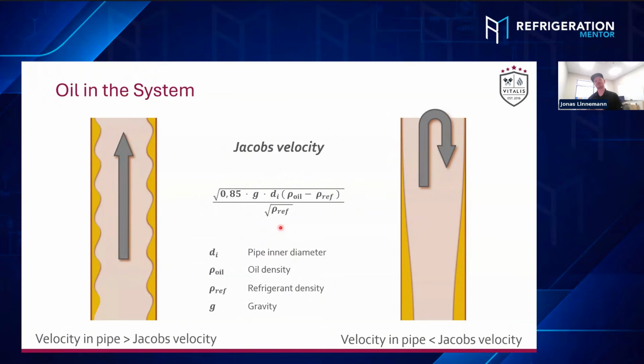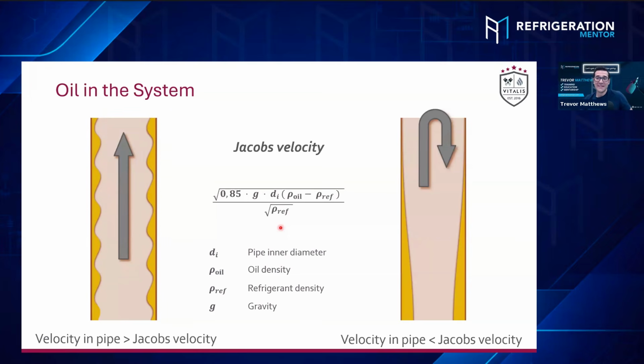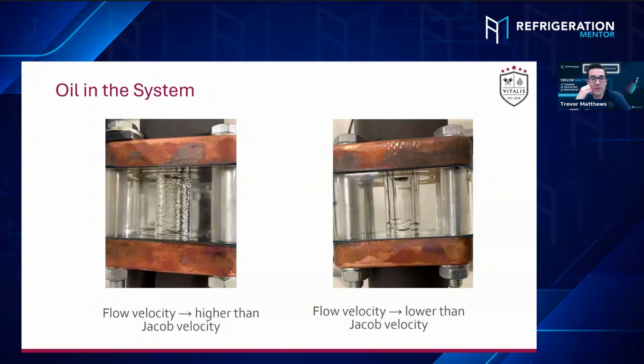So if we have whatever, like 6 or 8 meters per second in mind for the minimum velocity for HFCs, CO₂ sometimes still works with like 2 meters per second because the vapor is so thick, it just carries more oil with lower velocities. But on the other hand, the part load conditions for CO₂ are sometimes worse. So it's more like leveraging hours. There's a happy medium there, right? Because then that'll come into where you'll have double risers and stuff like that. And I think we'll talk about that in a minute or two.